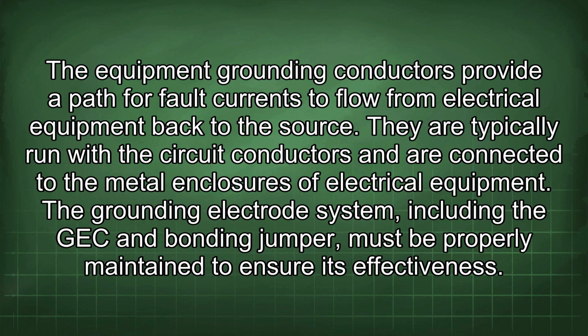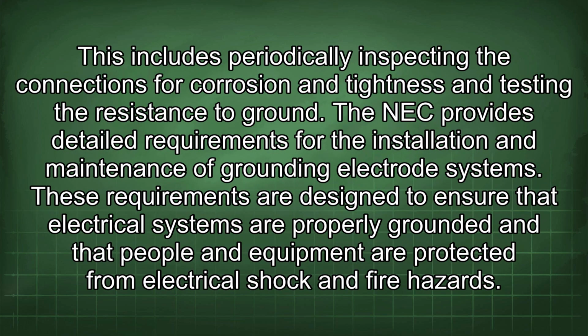The grounding electrode system, including the GEC and bonding jumper, must be properly maintained to ensure its effectiveness. This includes periodically inspecting the connections for corrosion and tightness and testing the resistance to ground. The NEC provides detailed requirements for the installation and maintenance of grounding electrode systems. These requirements are designed to ensure that electrical systems are properly grounded and that people and equipment are protected from electrical shock and fire hazards.